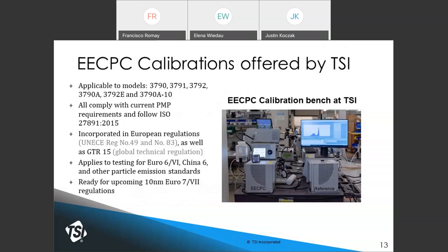TSI recently updated its CPC calibration process and consolidated all EECPC calibration services, available for all models going back to the initial 3790 — whether 3790, 91, 92, or the more recent 3790A-10. All calibrations use the same procedures and materials, are compliant with PMP requirements, and follow ISO 27891. These requirements are incorporated into European regulations and also apply to regulations in countries like China 6 and other particle standards.